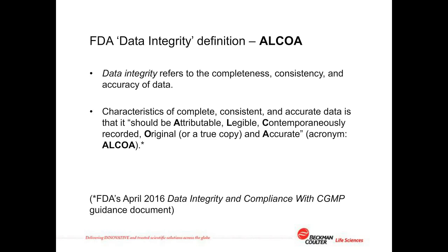So the FDA go on to talk about the characteristics of complete, consistent and accurate data, and they say that it should be attributable, it should of course be legible so you can read it, it should be created contemporaneously, and it preferably should be an original, or if not, a true copy, and of course it should be accurate, and this makes up the acronym ALCOA.